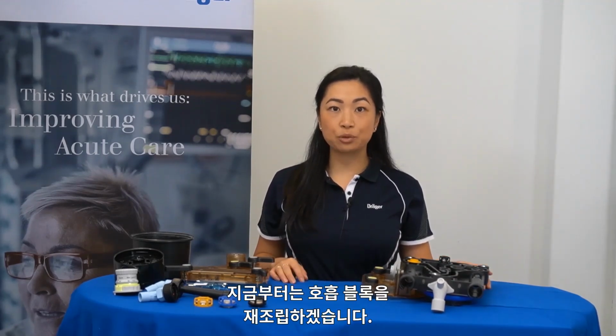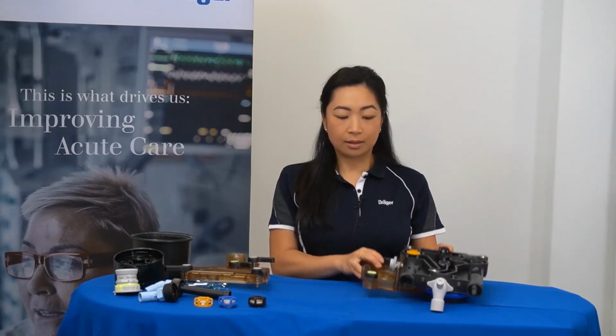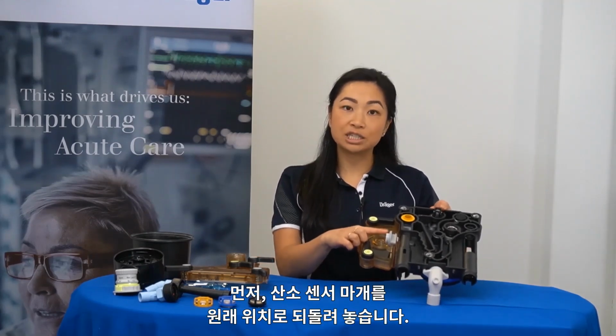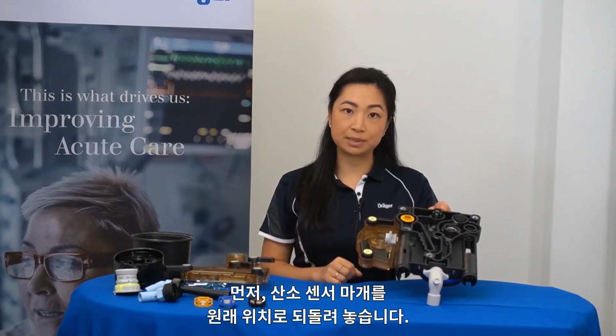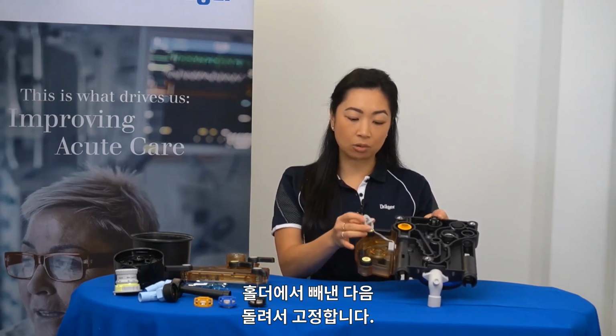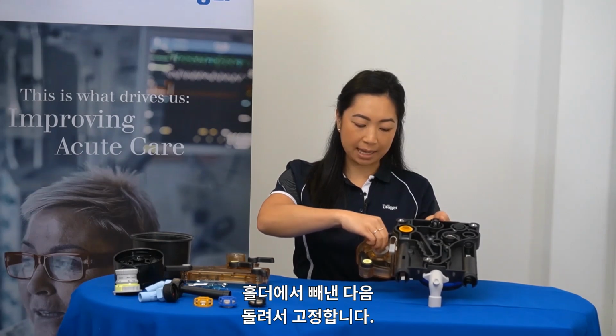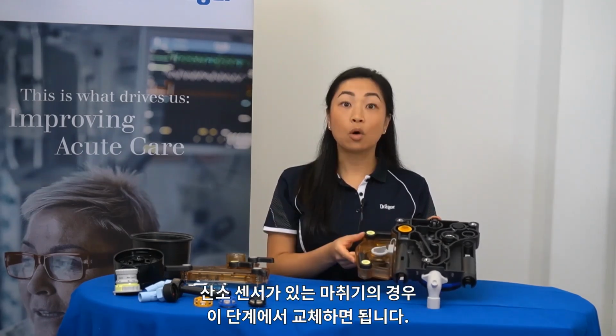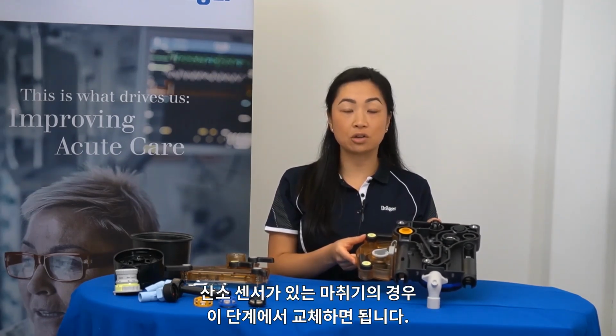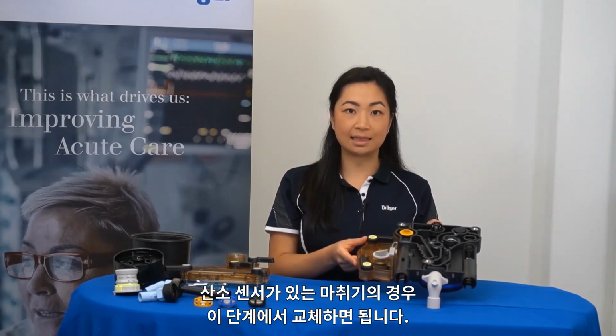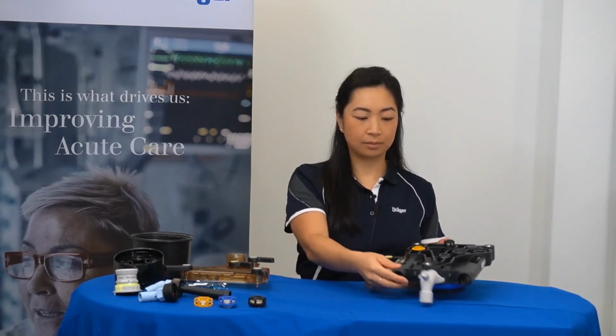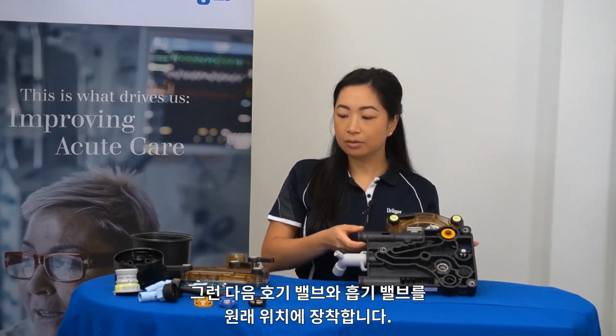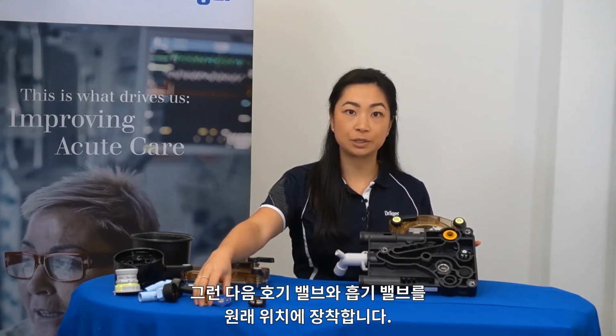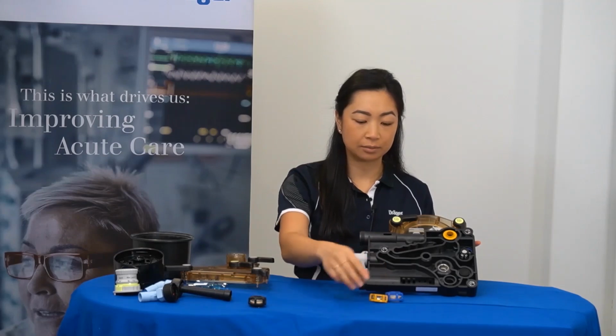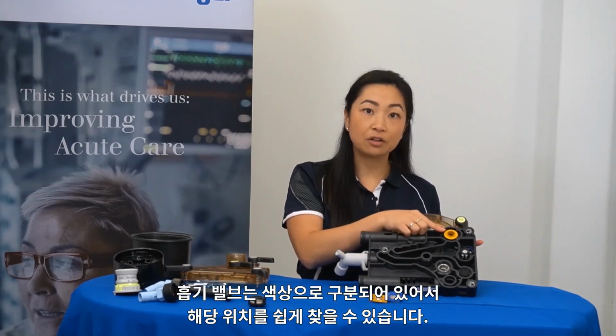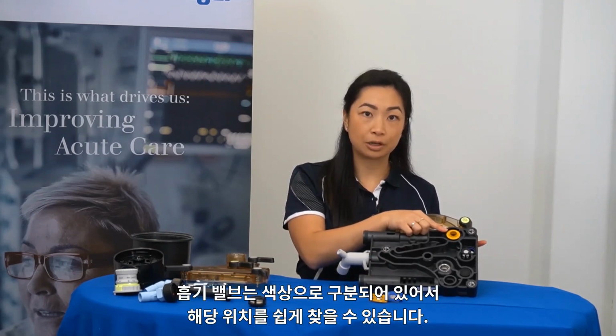Now to reassemble the breathing block. Begin by returning the oxygen sensor cap to its original position, taking it out of the holder and screwing it back in. Or for the devices that have the oxygen sensor, replacing that at this point. Then returning the expiratory and inspiratory valves to their original position. The inspiratory valve is colour-coded to help locate its position.